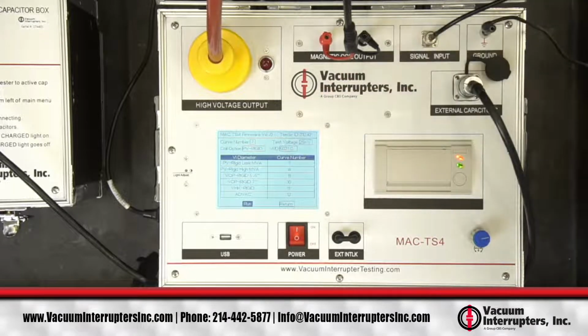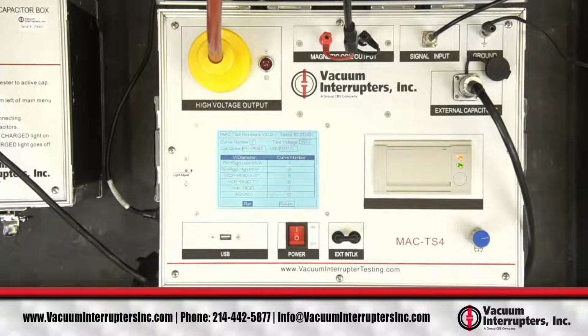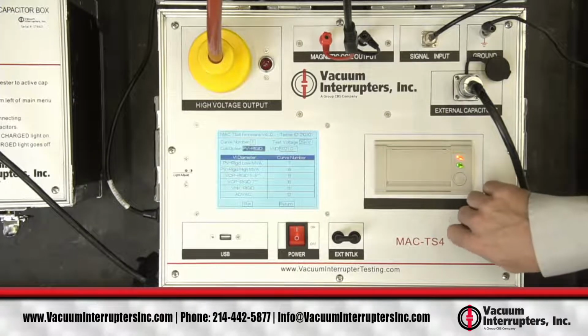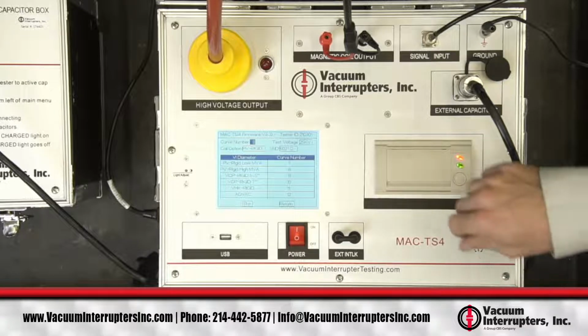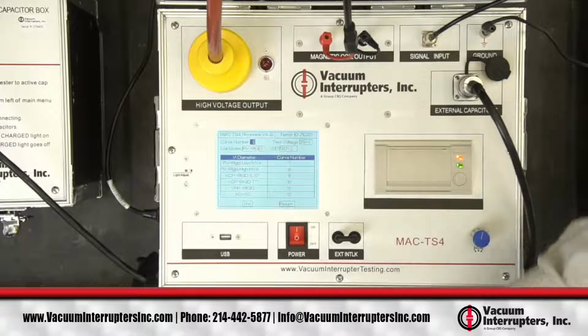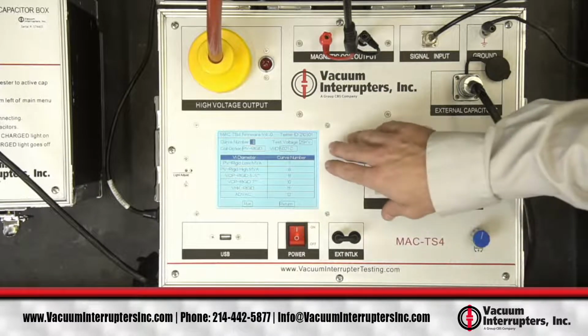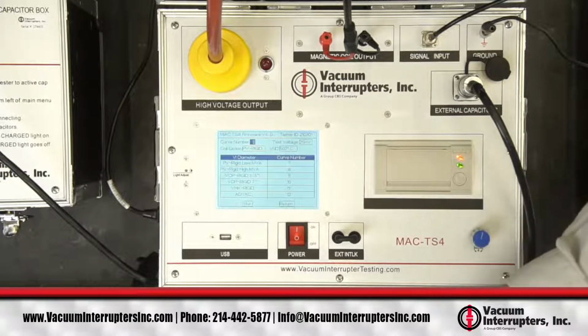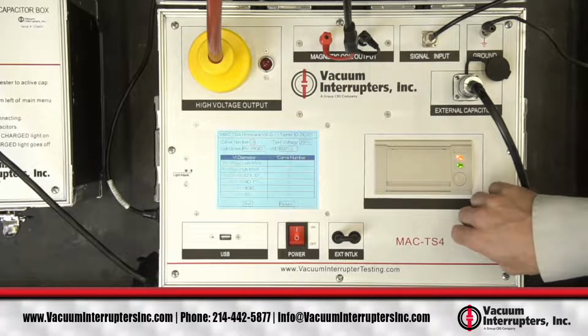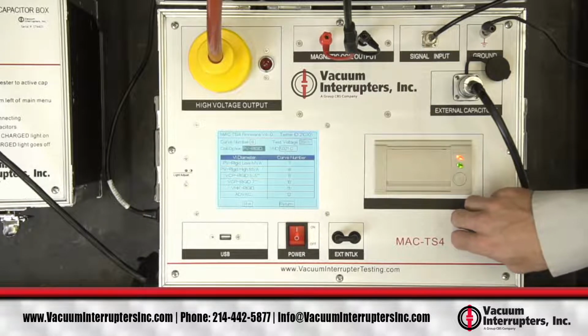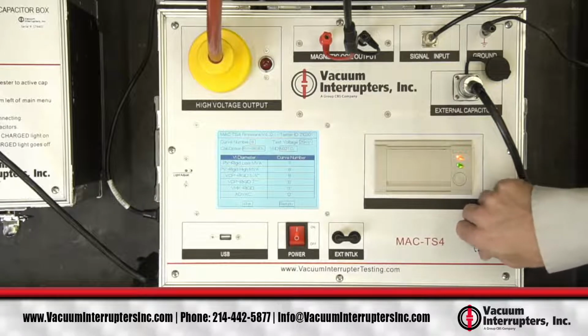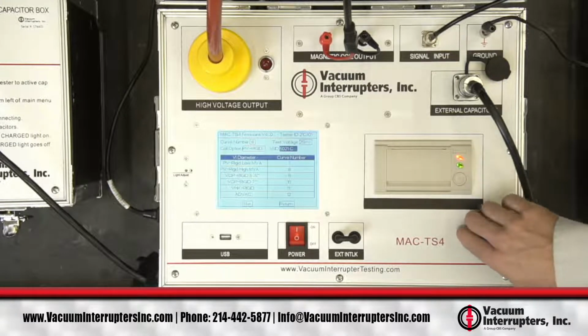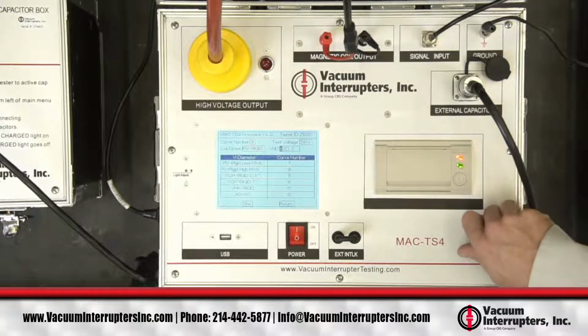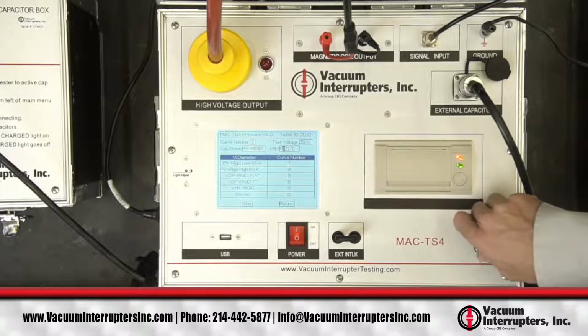We also have a different coil option. So in this case, we have the high MVA Power Vac, PV rigid VIs. So this would be curve 8. Just for reference, low MVA are going to be the smaller diameter VIs, which are about 5 to 6 inches. High MVA are going to be the larger diameter VIs, which are about 8 inches in diameter. So curve 8, our test voltage is going to stay 25 kV. Our coil option has now changed to PV rigid. You can't select any other type of coil unless you have other coil options that you've purchased. And then again, you can put in some type of reference here. It's alphanumeric, so you can put in whatever you'd like. I believe we've got 8 or 9 characters.